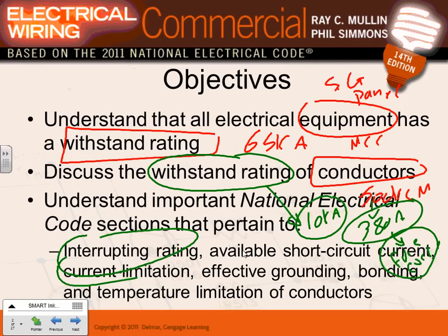But withstand means you withstand, you don't interrupt. You just stand there and handle that heat and the shaking, right? Interrupt, you're not going to stand there. If you're a circuit breaker and you see 65 kiloamps, you're not going to sit there and wait for it. You're going to interrupt it as fast as you are set to do that.